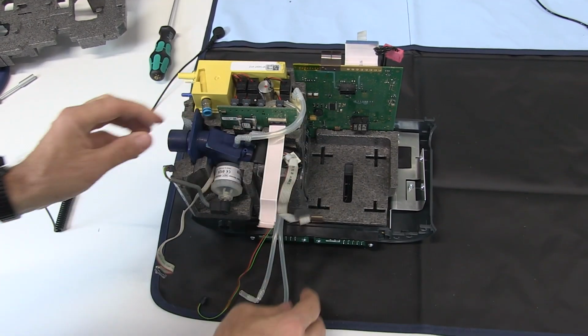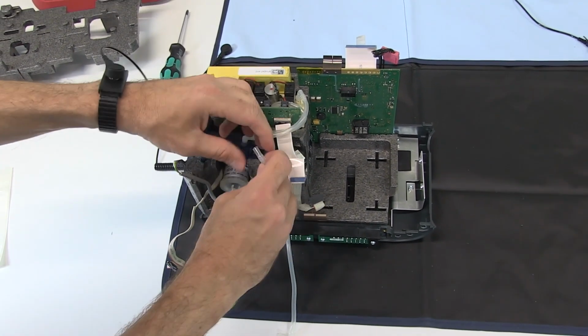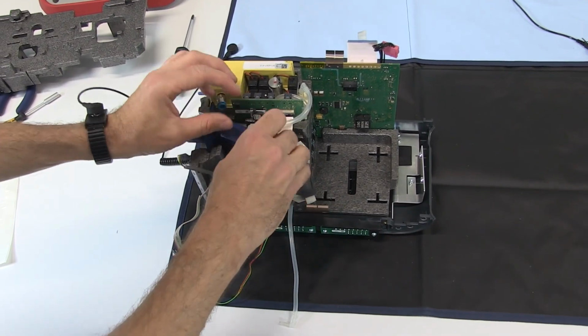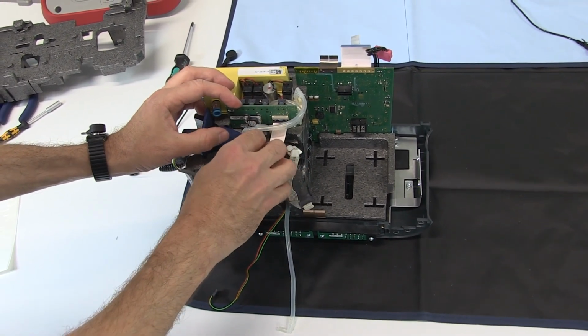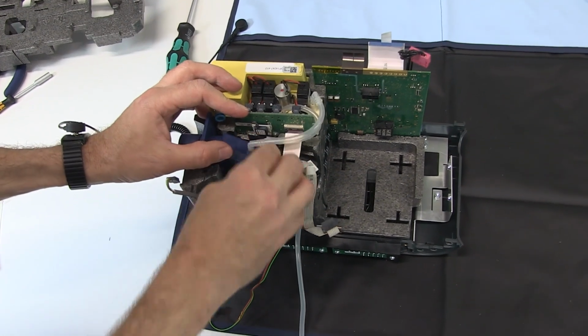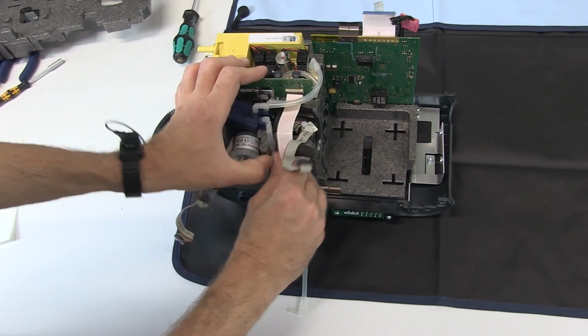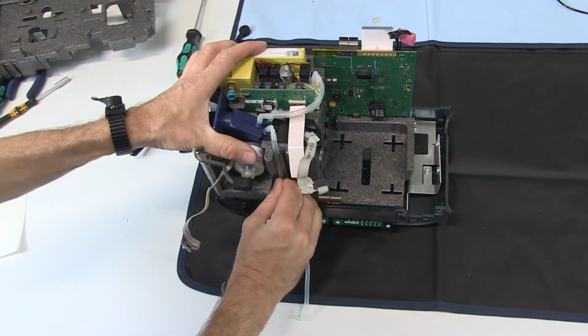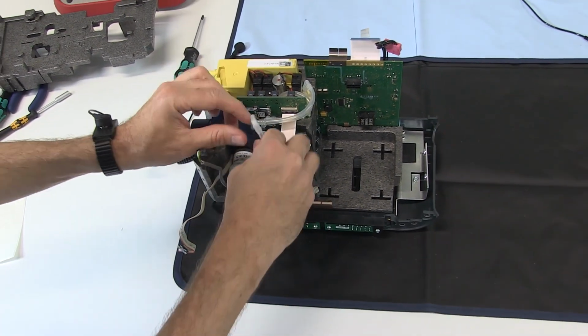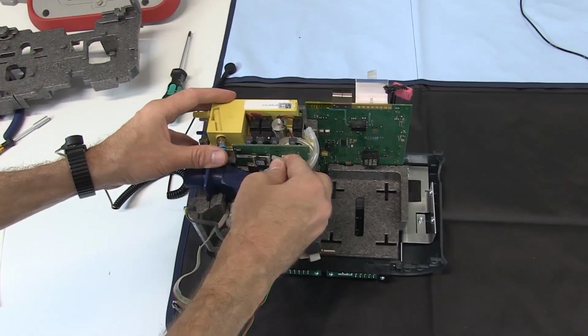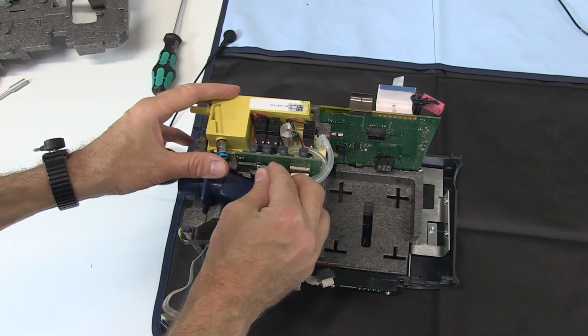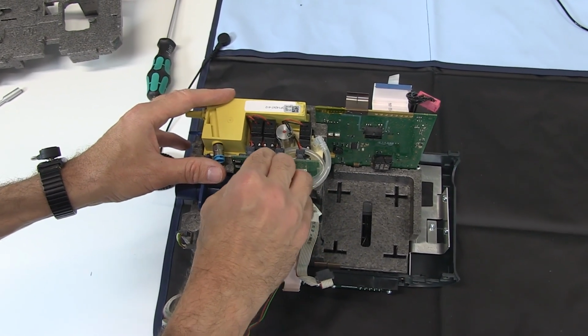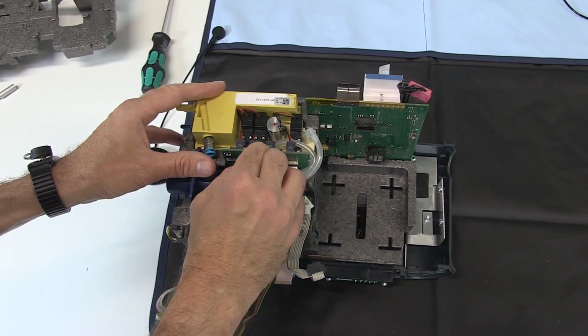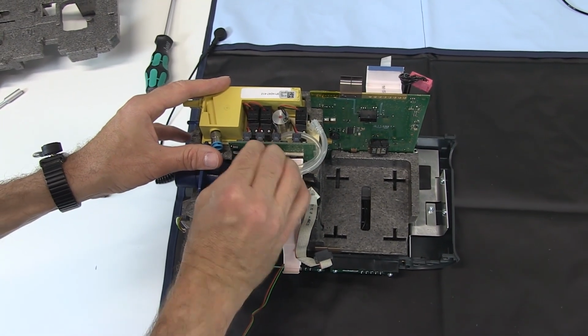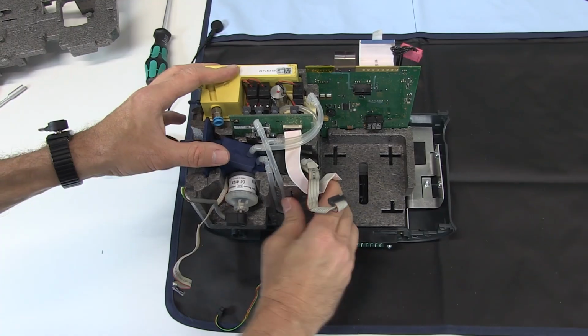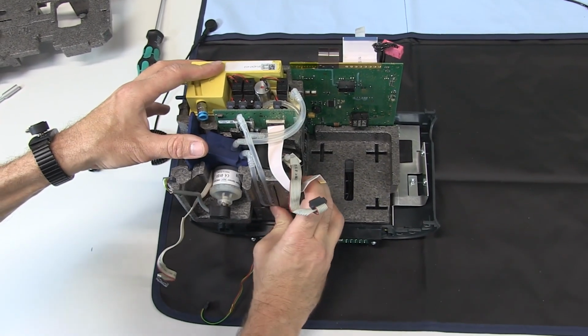Then connect the expiratory proportional valve tube from the expiratory valve assembly to the designated port on the check valve assembly. Connect the PX valve tube from the expiratory valve assembly to the designated port on the pressure sensor assembly. Ensure the tubes are correctly connected to their individual ports and that you push the tubes inside the grooves in the middle foam to keep them in position.